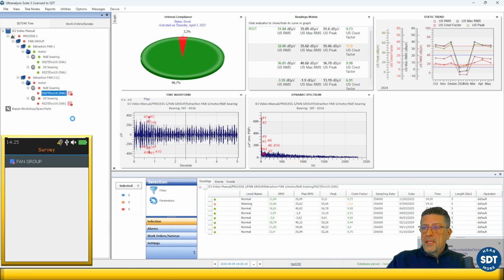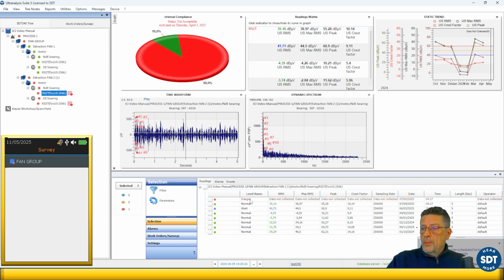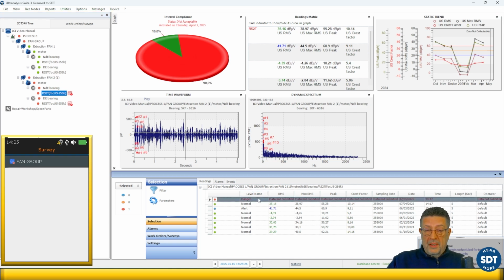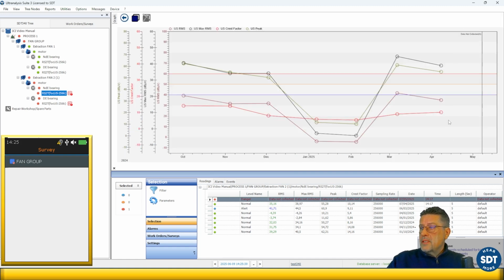And what I can see here, it's very important also to mention that the moment this status is assigned to this measurement point, the data was not collected, something happens in my trend as well. The trend has a hole. So here is the message, data not collected. Now, what happens quite often is that this dot and the next dot after I'm 2 or 3 months late are connected. So it looks like everything is in continuation, while in reality it is not. So for everyone who is looking at a trend and trying to understand it properly, this will be a great help, because we know that between this measurement and that measurement, it's a hole. We don't have the data. We don't have knowledge of what the situation was at that time. So it will simply stay a hole. It will not connect with the next measurement.